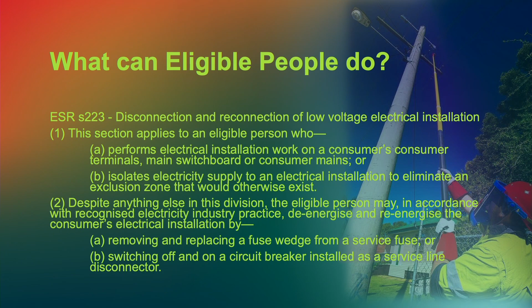So what can an eligible person do? Under ESR section 223, there's a section titled Disconnection and Reconnection of Low Voltage Electrical Installations. In part 1, it sets out that the section applies to an eligible person who performs electrical work on a consumer's terminals, main switchboard or consumer main. So they may be preparing repair work or any other replacement of the services. Or B, they're isolating supply to an electrical installation to eliminate an exclusion zone that would otherwise have existed. A lot of times we're doing that for other trades like painters and roofers and gutterers to make sure that they're safe when they're working in the vicinity of an overhead line.